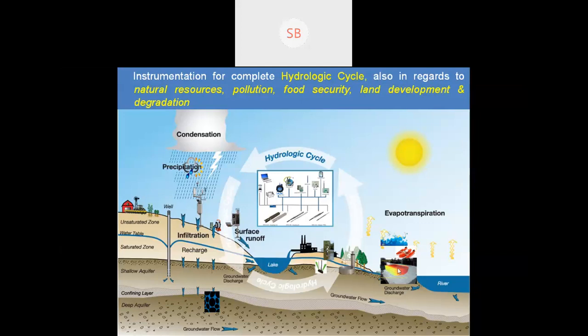Again, the problem is that during the flooding season, you cannot use an ADCP to run across the flow, which is not possible. So this exercise is done pre-monsoon or post-monsoon to get the profile, and the surface velocity alone is normally measured using a camera based system. From the pre and post monsoon profile you calculate your discharge. So this is how you are able to get better accurate data. The data is more, it is going to be voluminous, and it is going to be accurate also.